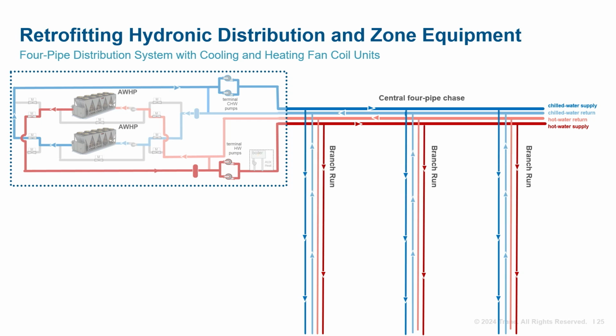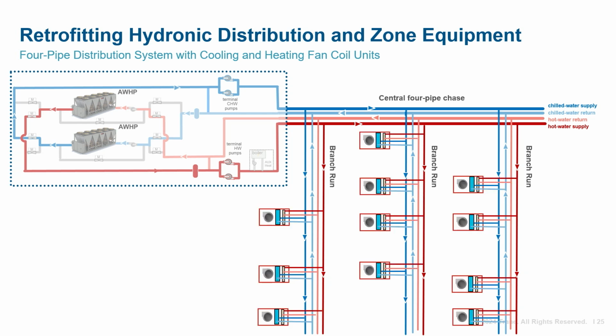The 4-pipe distribution system is not dependent on the type of heat pump equipment used in the central plant. For our example, the air-to-water heat pump is 2-pipe, but can be utilized in a 4-pipe distribution system. Piping branches off the central chase to areas of the building. This piping brings the heating and cooling fluid to and from the zones. Then zone piping runs to and from these branches, as required by the zone unit. Most existing zone fan coil units are also 4-pipe, containing a heating coil and cooling coil, and a fan to force air through the coils to exchange the heat either to or from the zone. And they have coils sized for 45-degree chilled water or colder, and small heating coils sized for 140-degree hot water or hotter.